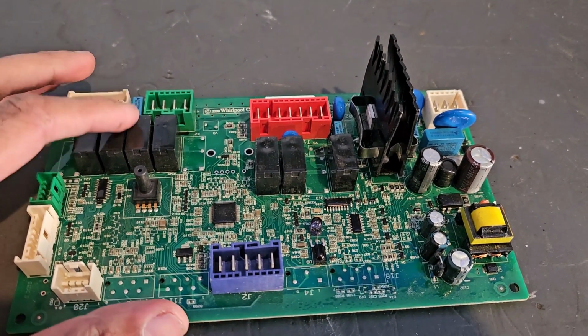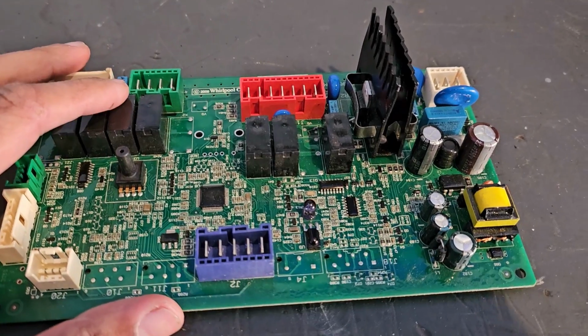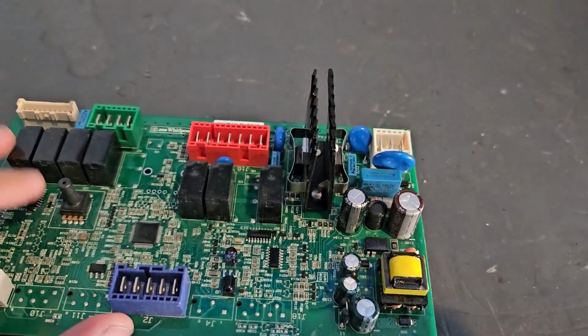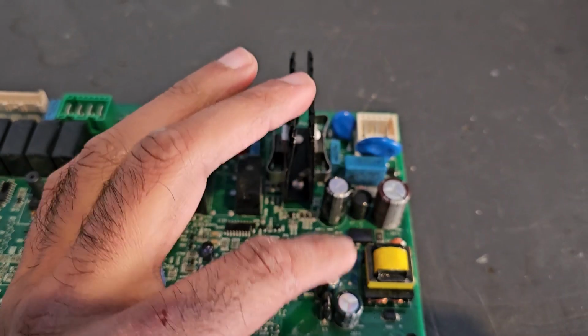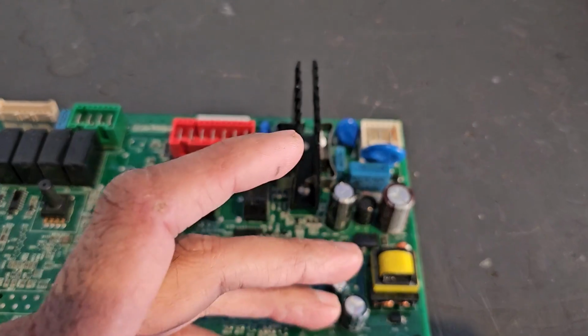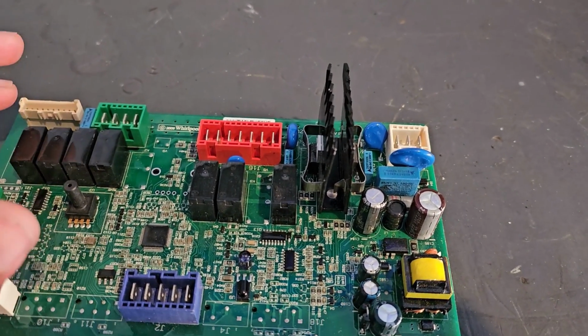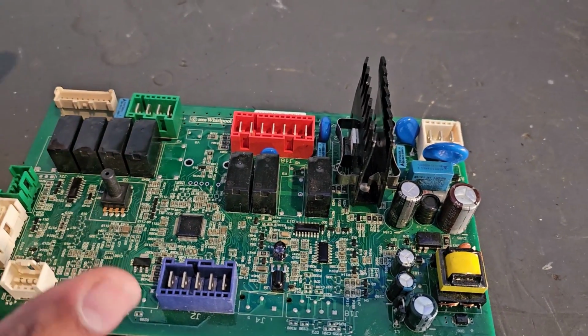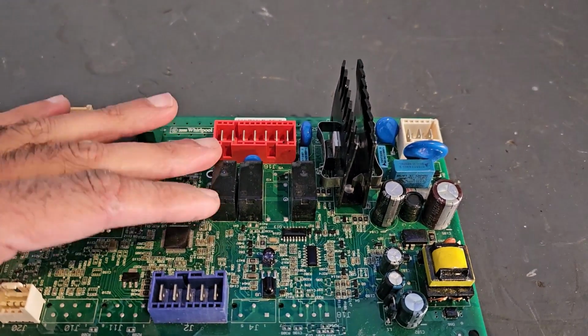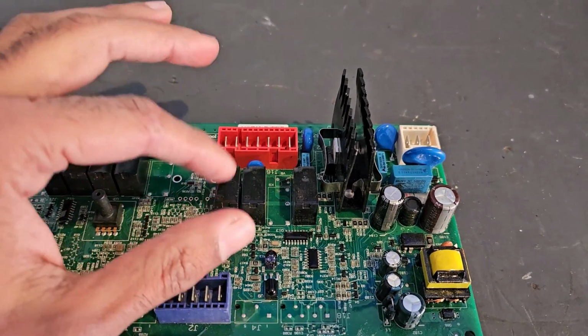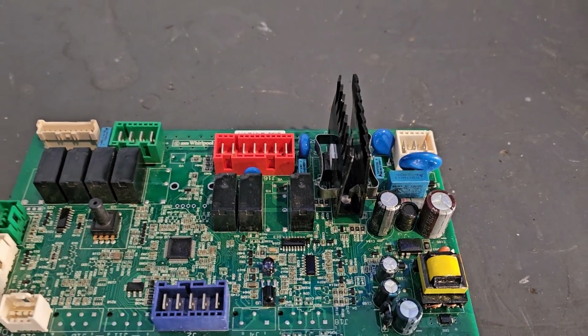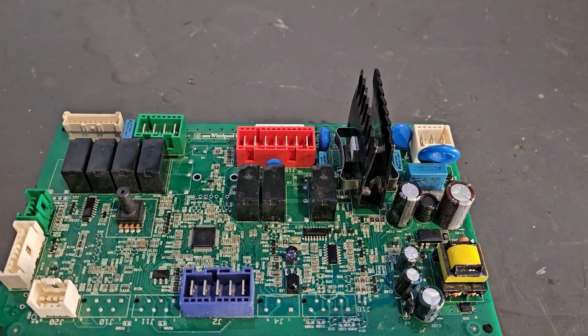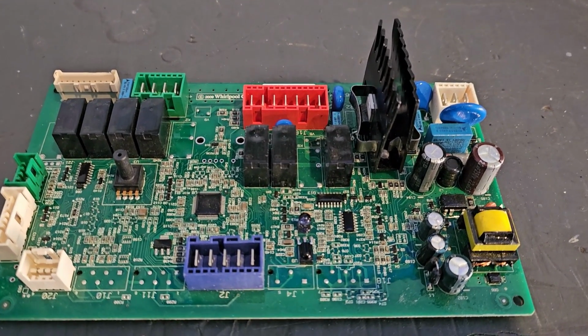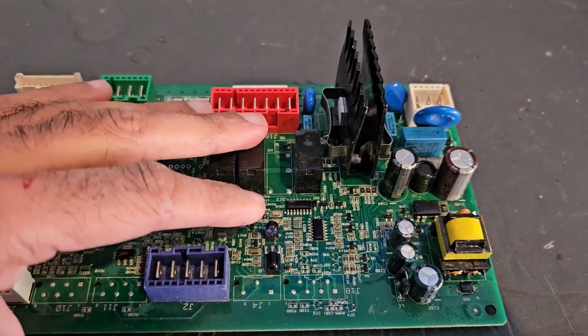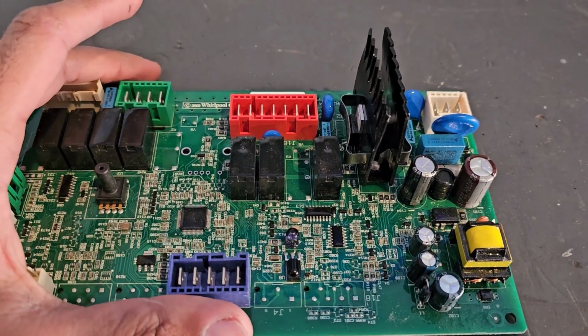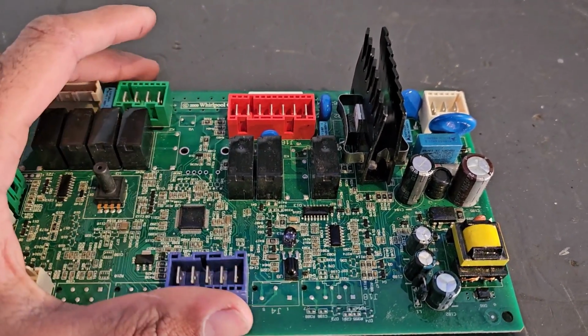And these issues are often repairable, because most of the time these issues are from two main components that have gone bad. One, either it's an issue with the capacitors, which is mostly what we're going to be dealing with in this video. And the second main issue is relays, which I'll try to cover in another video. Sometimes these things can get stuck or they can burn out, which can lead to issues. But those two issues are often the cause for a lot of control board problems. And it's a shame to have to throw away an entire control board for something that small. Plus, these control boards are not cheap.